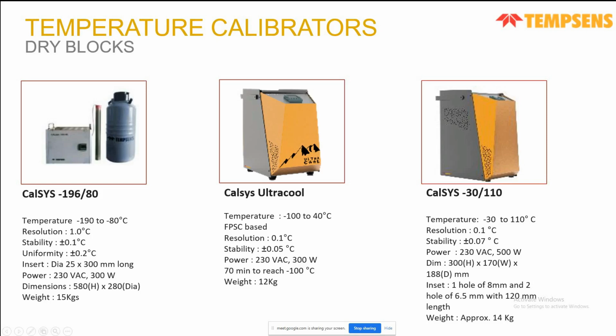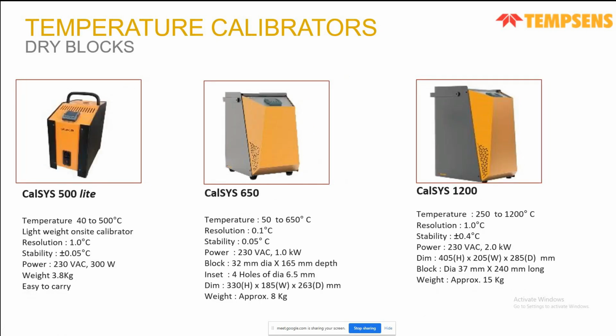This is using Peltier, -30 to 110 degrees centigrade. So they have got blocks in which you can put your master and test sensor and can do comparison calibration. This one is a light model, so it is just less than 4 kg, so you can easily carry it to site. Temperature range is 40 to 500 degrees centigrade.